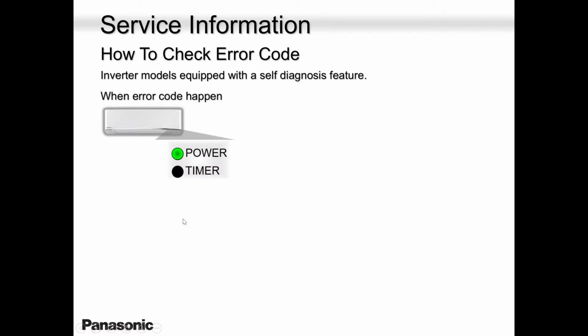I spoke about how easy it is to retrieve our error code, guys. This is what you can ask the homeowner to do. If the homeowner calls you and says the timer light, okay, guys, the timer light, not the power light, but the timer light is blinking. Okay, when the timer light blinks, you have an error code. When the power light blinks, the unit is in defrost cycle. Please write that down. The difference between green light power and yellow light timer. When the timer light blinks, you are in an error code state. When the power light blinks, you are in a defrost state. Okay, so when the homeowner calls you and says power light is blinking, that's defrost cycle.